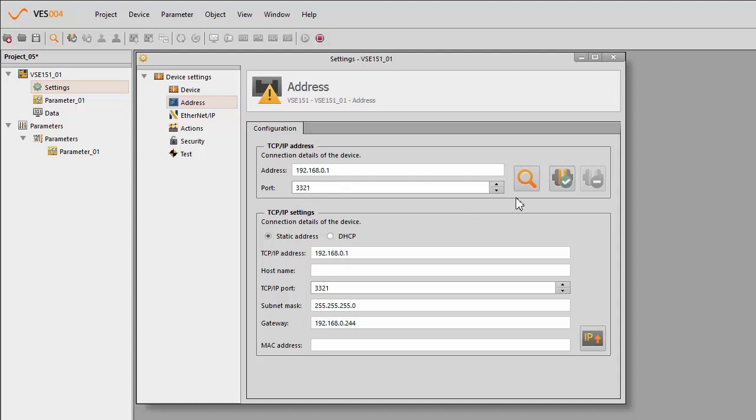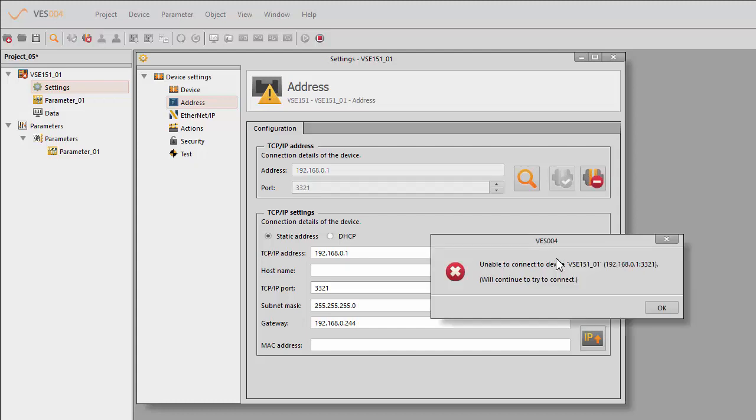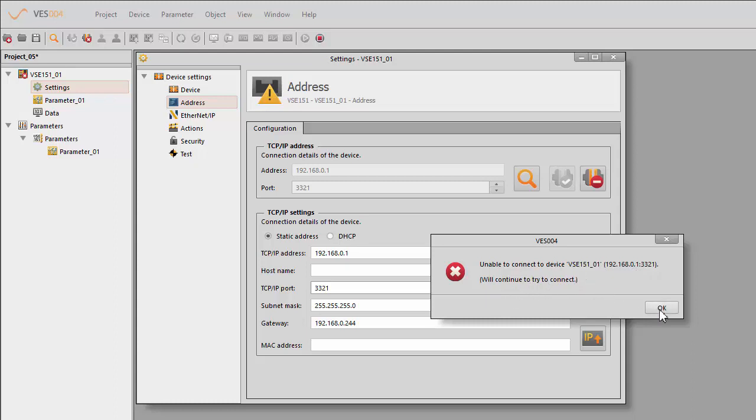If I try to connect now, as most people will try to do, it won't work. It's taken too long to actually connect. Normally it happens in a few seconds. You see there, it's unable to connect the device to the VSE151 at the default address, and it will continue to try. We'll select OK. The reason it's not talking is we don't have a setting right.